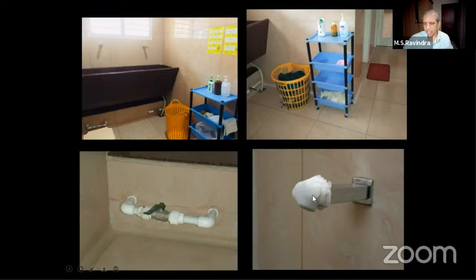It should be clean. It doesn't have to be sterile. But what it does is, if there is some amount of contamination on the lines, at the end of the day my staff open it up and inspect it and touch it and see it under a microscope in bright light. If there are suspended particles there, that means some amount of contamination is somewhere on the line, and you will see it may be blackish or it may be slimy. So that has to be taken.